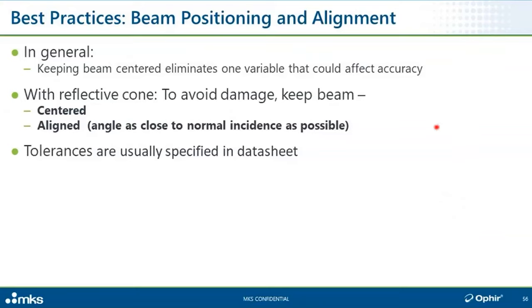Okay, some more best practices, beam positioning and alignment. In general, as far as possible, we recommend that you keep your beam centered, because when we calibrate the sensor, we keep the beam centered. And when you do your measurements, if you do the same, then you've just eliminated the variable of uniformity of tolerance across the aperture. You've eliminated that as a variable that could affect accuracy. I'll also mention that we usually keep the beam to somewhere between 1/3 and 2/3 of the full aperture. Won't go into that now, but you're eliminating the small localized non-uniformities from having an effect, and you're also keeping away from the damage threshold. But on the other end, you're also keeping the beam not too big so that you don't unwittingly chop off some of the outer bits of it by the aperture.